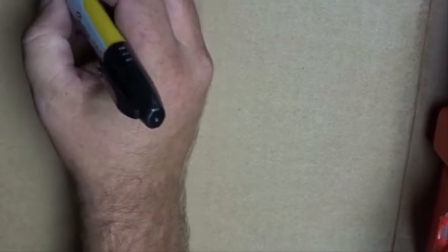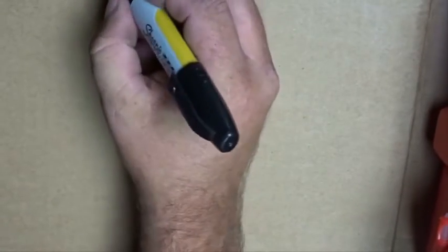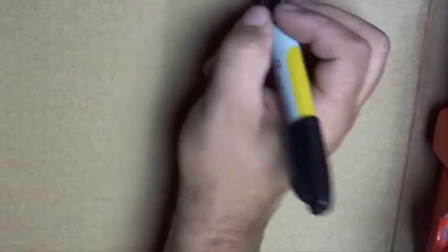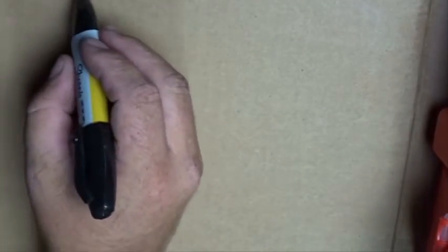So I'm going to show you how I put them into the circuit. What I typically do is I will put them in the Y, and we're talking about Y as equaling the contactor circuit. That way it will shut off the AC. If you shut off everything like with the red, you don't have the blower to help everything thaw out if you're having a freezing issue. If the blower is left running, it'll warm the sensor back up and we'll start the process over.